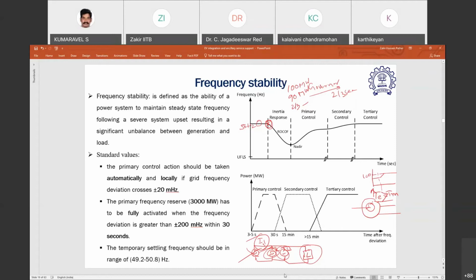Because of the higher electrical torque compared to the mechanical torque, which, as I mentioned, cannot change instantly. Electrical torque can change instantly. That is the beauty of electricity, and that's why loads are shifting from other sources to electricity. It is fast, the control is very fast, the transportation is fast, it is more efficient. So that is precisely what is happening here. By the very natural characteristic of electricity, the electrical torque is changing instantly, but mechanical torque cannot change. What does it mean? The machine is getting more burden. Since it is a synchronous machine, what will happen? The speed of the machine will start slowing down.